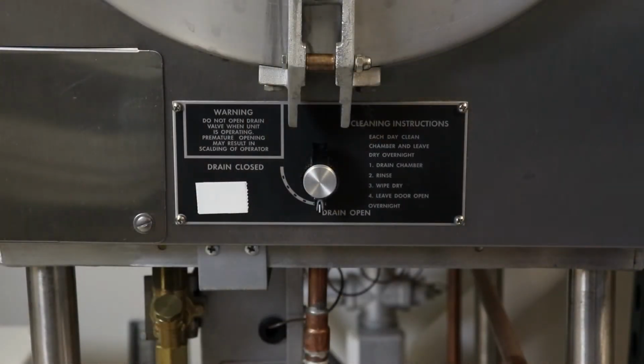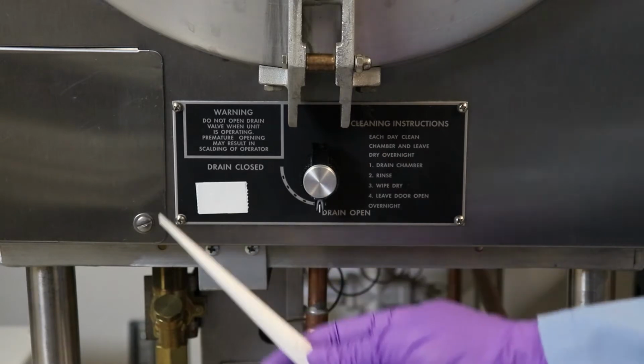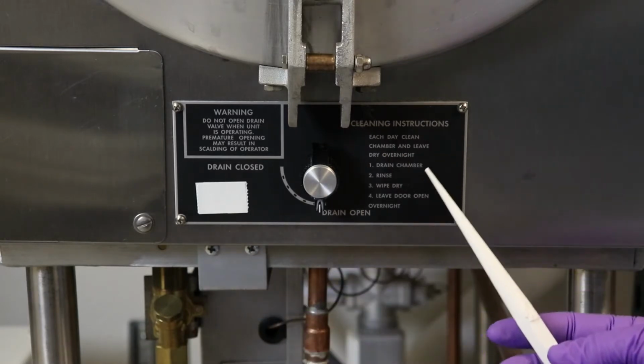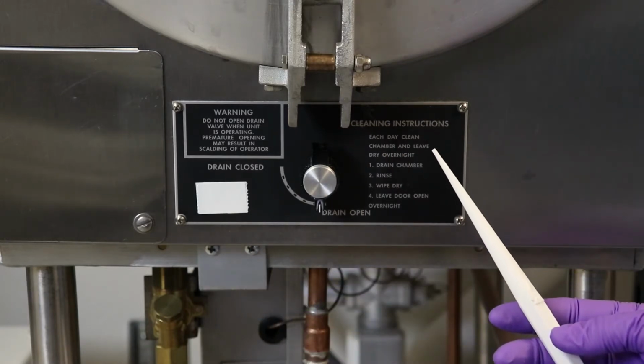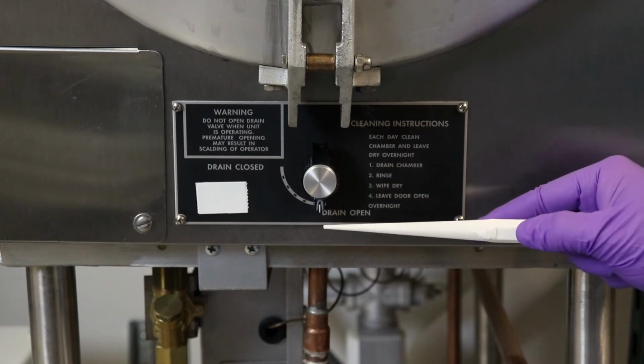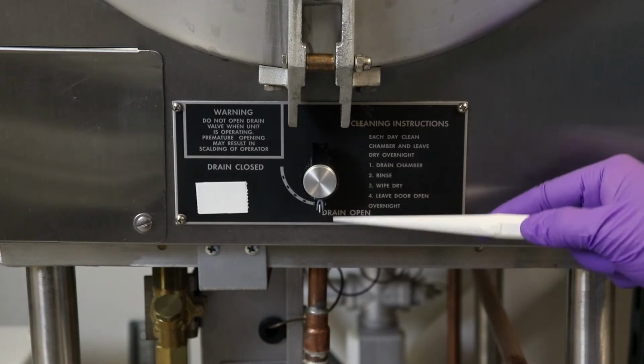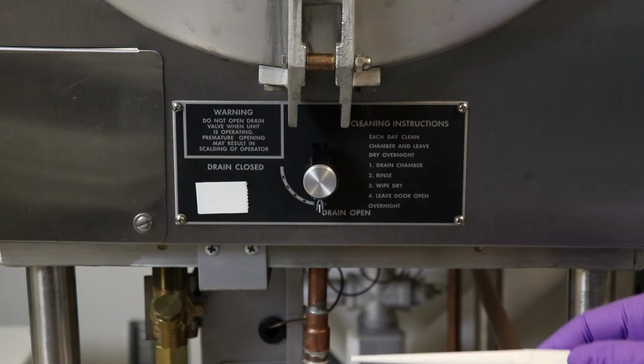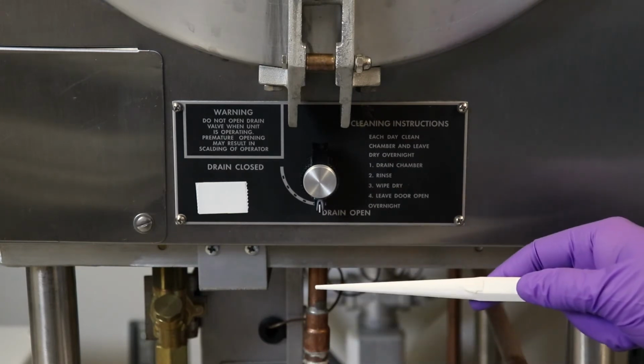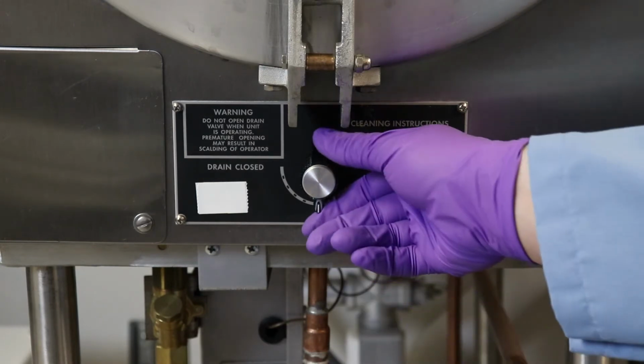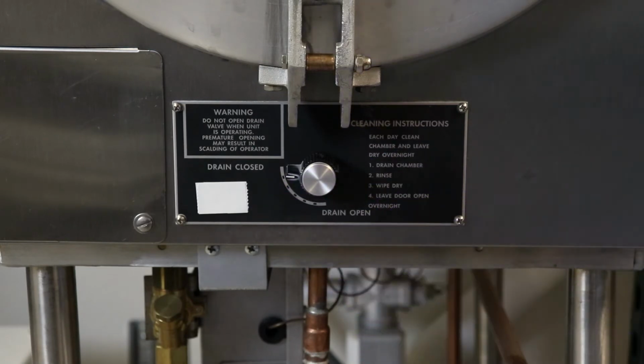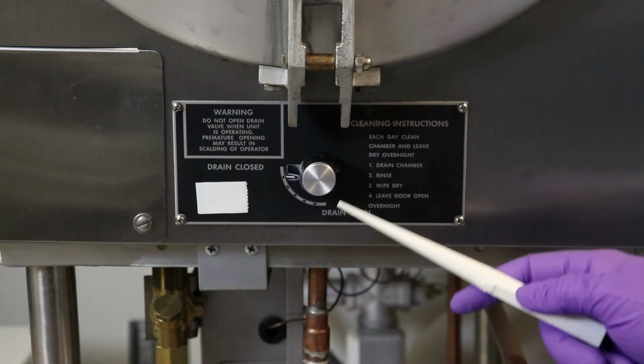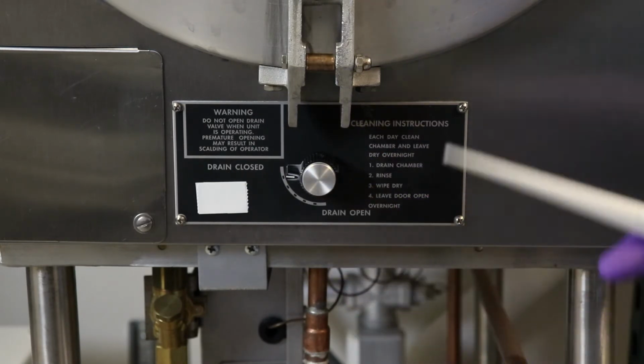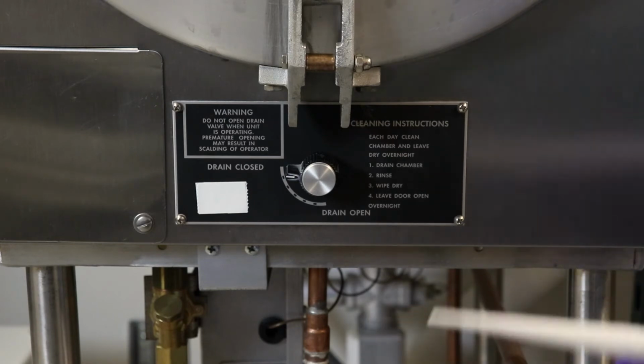The last section of the autoclave is the drainage valve. This is used to drain off water after a cycle is completed. In the downward position, the drain is open, and any water that goes into the chamber will come out through the bottom. When shut, you just twist it to the closed position. You will feel a stop as you turn, and now the drain is closed, and any water that is put inside will stay inside the chamber.